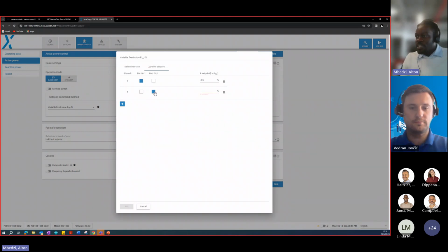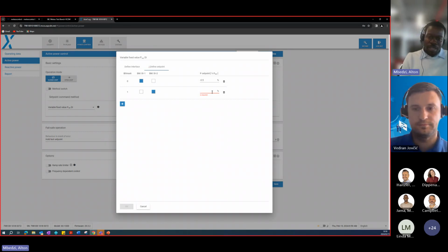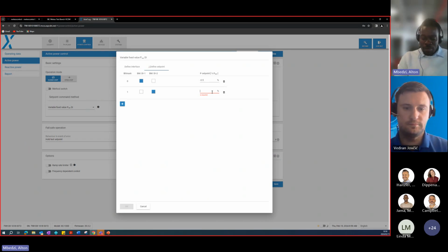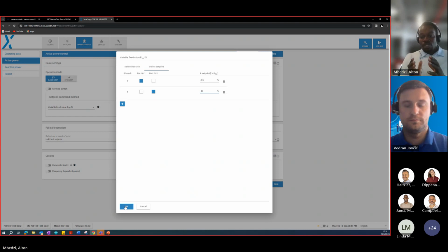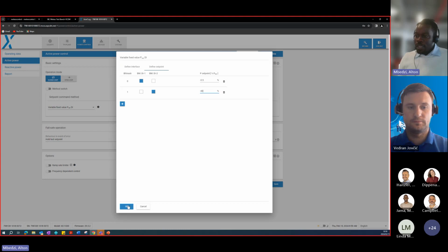So let's say, for instance, if it's normally closed, what do I want to do? Because this is on the generator side. Let's say your generator has a prerequisite that says we need you to always maintain 40% of the generator's capability. So you can say, okay, 40%, minus 40%, so you always maintain that you take minus 40% from the generator. But bear in mind, the meter control doesn't control the generator, it controls the PV. So it will work with the PV to throttle it down to make sure you maintain 40% from your generator. Then you just click OK.